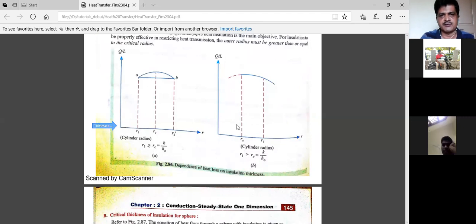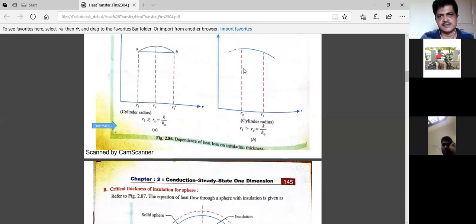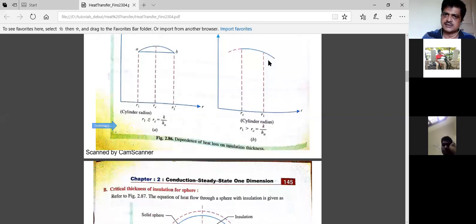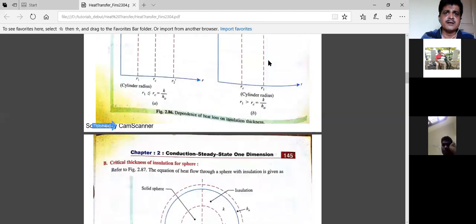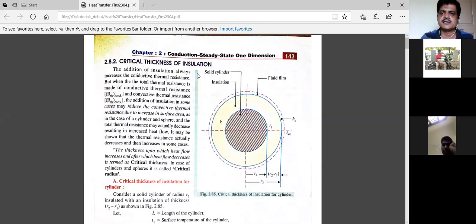For thermal insulation, the insulation radius should always be kept greater than the critical radius. As you can see in the graph, heat transfer keeps on decreasing when the thickness of insulation is increased beyond the critical radius. This derivation gives the critical thickness of insulation for a cylinder: rc = k/h₀, where k is thermal conductivity and h₀ is the heat transfer coefficient.